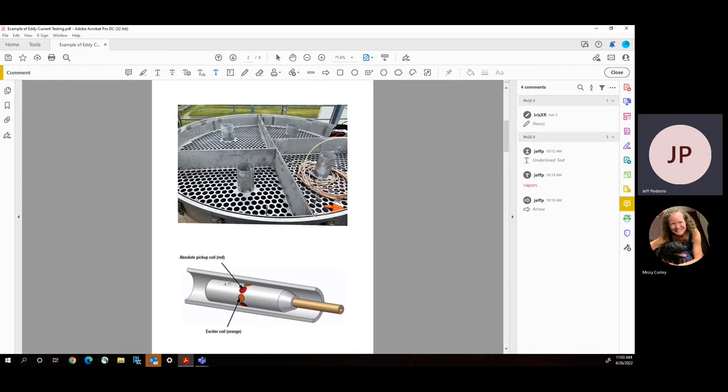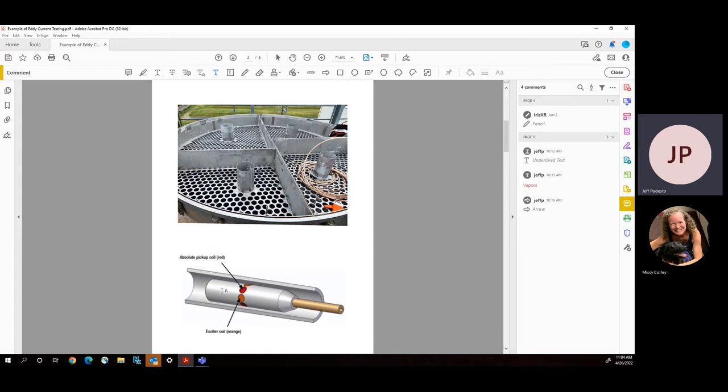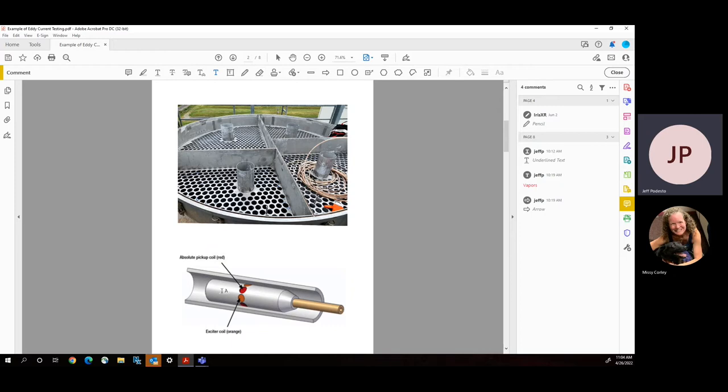What the system does is it actually puts this probe into a reference tube, which has no failures or flaws in it, and that sets the target or what a clean and new tube should look like. And then we send the probe down the tubes that are on the evaporator, and the differences between the reference tube and the actual tube is what allows us to determine what's happening on the tube. The magnetic field travels out from the probe, and then the feedback comes back into the computer. And then we know the variance between a good tube and what's happening in the existing tubes.